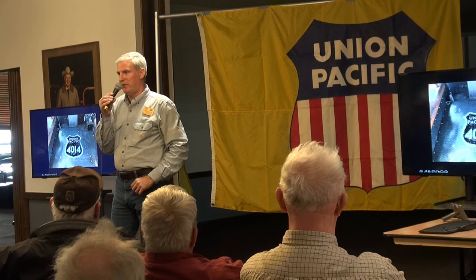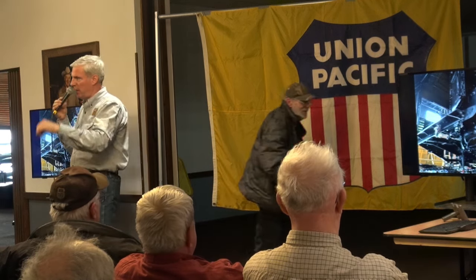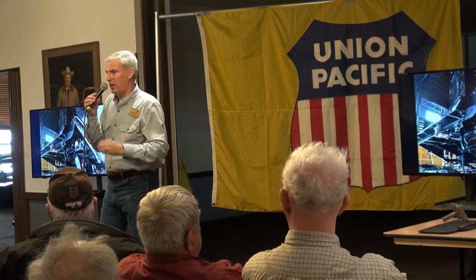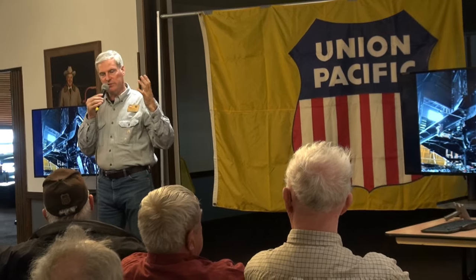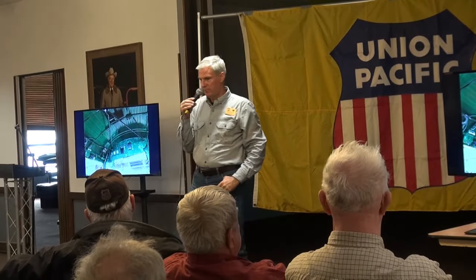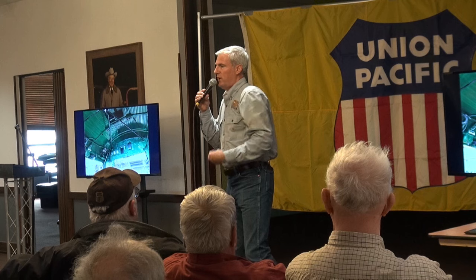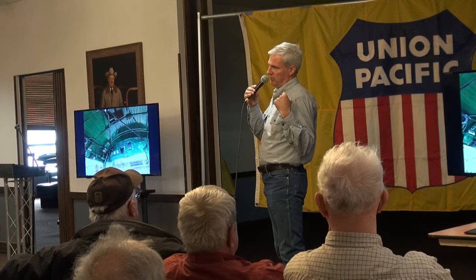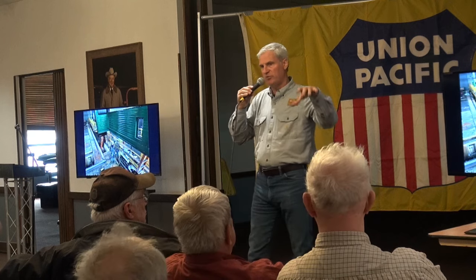It's a resin bead that's specifically designed, and it is not quite microscopic, but it's about the size of the head of a pin. And that thing is designed to attract the ions of sodium and calcium. So to get the system ready, you recharge it or you flush it with brine, with salt. So you take all the salt solution and you flush it through, you wash it. And those resin beads grab hold of those sodium ions and they populate those tiny little pinhead resin beads, trillions and trillions of them. And you run that through. And now you've got this giant resin bed, this tank full of these beads, ready to go.